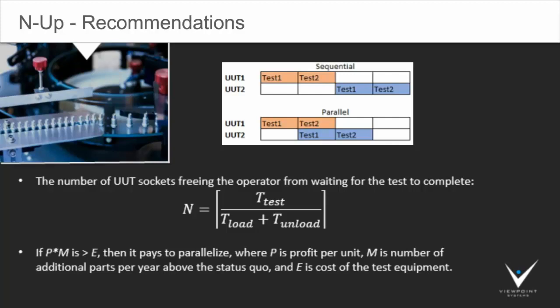Look at the illustration at the top middle showing an example of running a sequential test across 2 units versus a parallel test across those same 2 units. On the parallel side, if you can share equipment, you can test 2 parts at once. This is the benefit of an N-up tester.